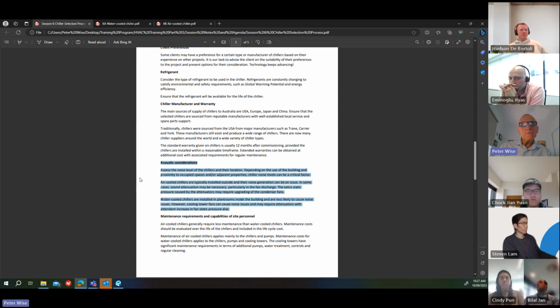Acoustic considerations. We need to assess the noise level of the chillers and their location. Depending on the use of the building and proximity to occupied spaces and or adjacent properties, chiller noise levels can be a critical factor. Air-cooled chillers are typically installed outside and their noise generation can be an issue. In some cases, sound attenuation may be necessary, particularly in the fan discharge. So we might have to put attenuators on the fans. The extra static pressure caused by the attenuators may require upgrading of the condenser fans.